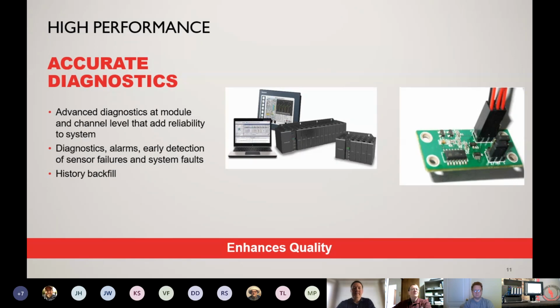One of the big things that we use quite often in the HC900 is the early detection of failure of thermocouples on the analog input board. The analog input board will actually send a pulse out onto the line and look for feedback to signify if that thermocouple is ready to fail, or if there's imminent failure on the horizon, where you might need to go out and change that thermocouple before it shuts your process down. So early detection is a big thing.